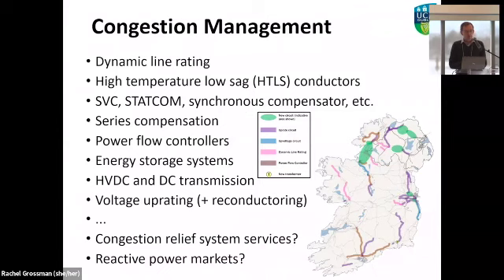There were questions earlier about grid enhancing technologies. There's a wide number of them: dynamic line rating, high temperature low sag conductors, STATCOMs, static VAR compensators, power flow controllers, batteries, and so on. The question is which ones to use, where, and what's most cost-effective. I don't have time to go through all of these, so I'll focus mainly on dynamic line rating, but also mention power flow controllers and energy storage.